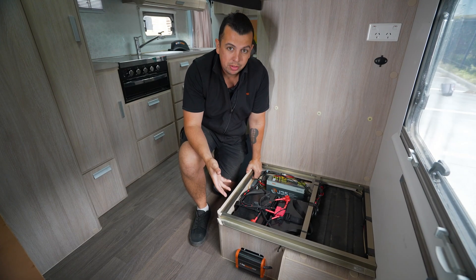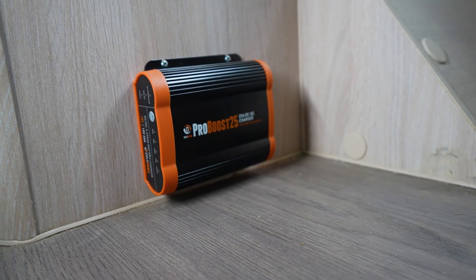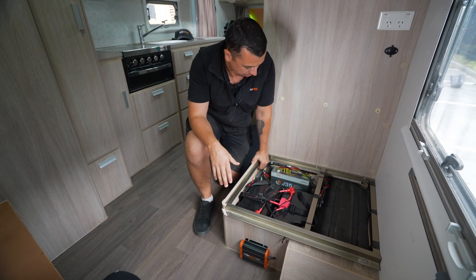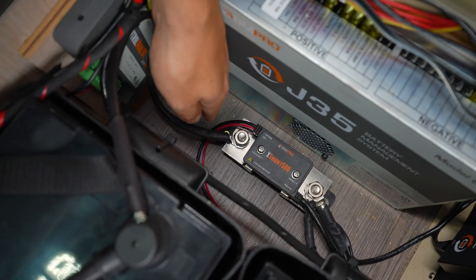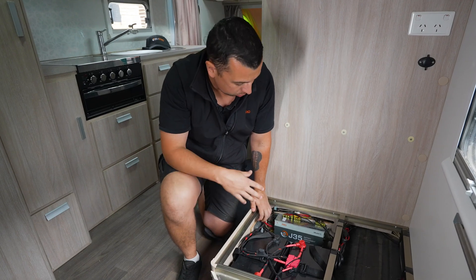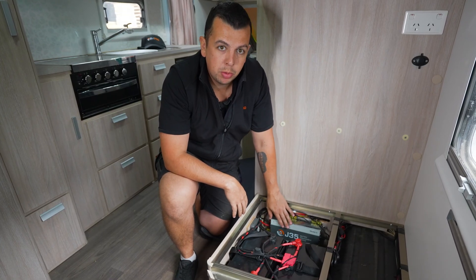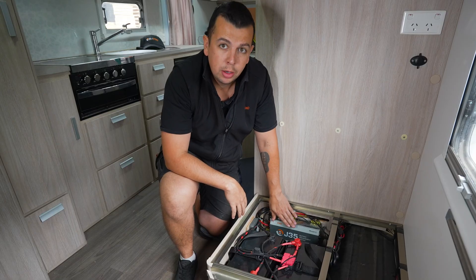This is a prime example of how you can upgrade these existing systems. As you can see down the front here, we've advised that the best scenario would be to fit a ProBoost 25, and to do this we've had to fit a PX Shunt 500 and the PX Gateway to allow the measurements of that charging to be read by the system. We've also recommended that his system was removed and sent to us, and our service department was actually able to upgrade it and load the latest firmware for this unit.